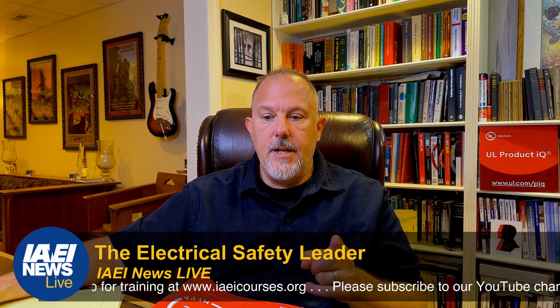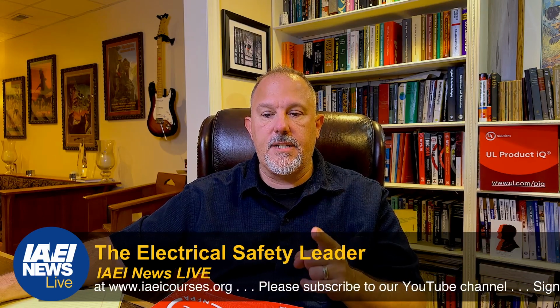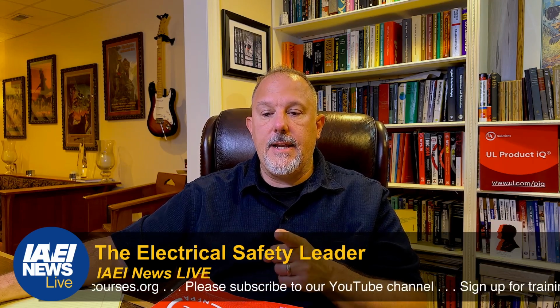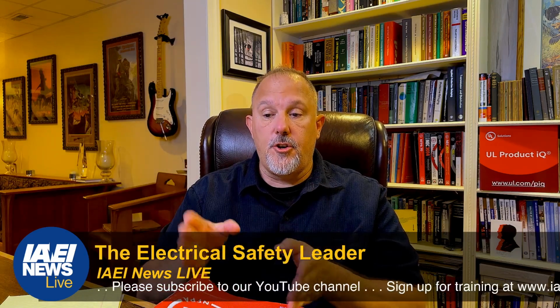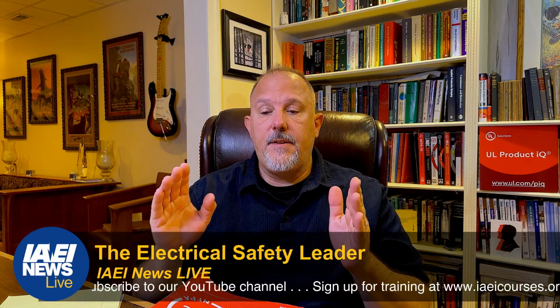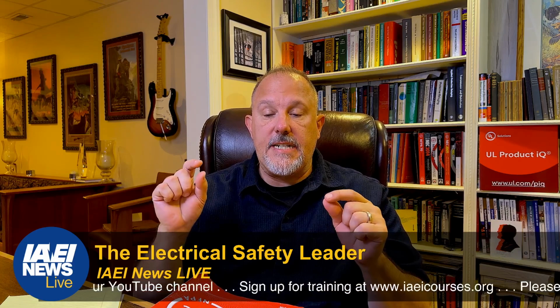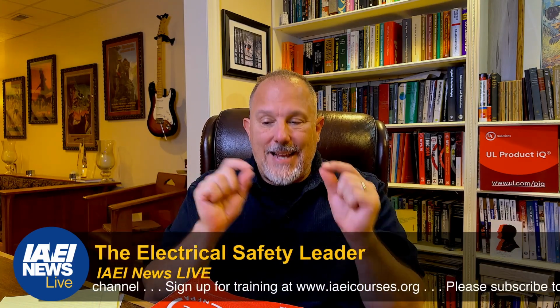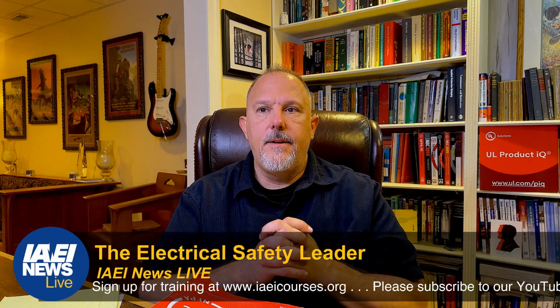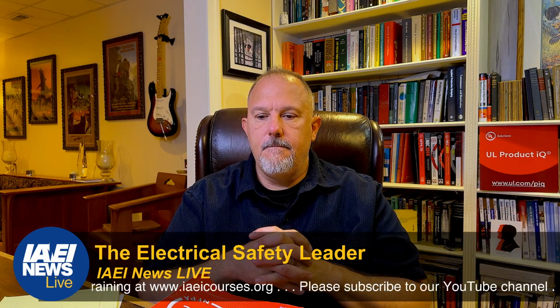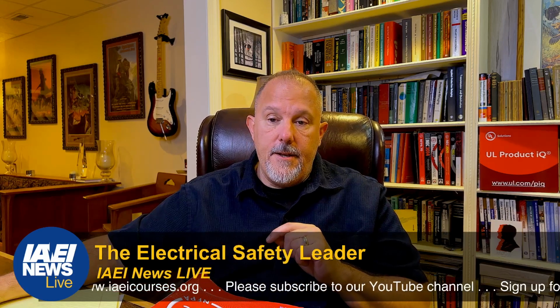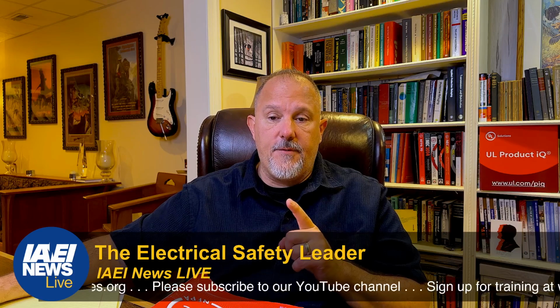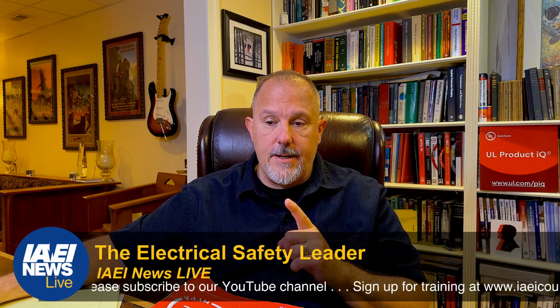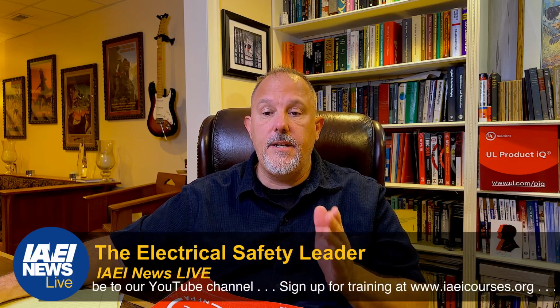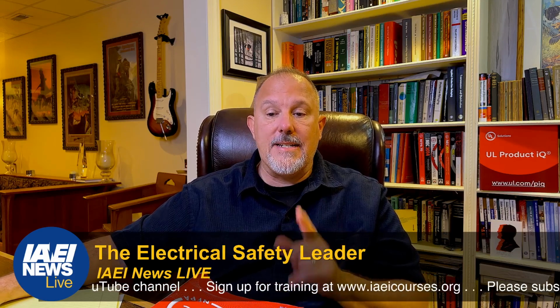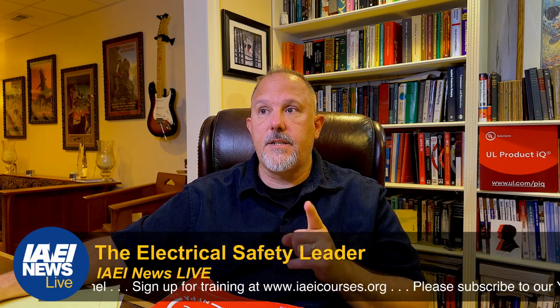related to surge arrestor, and it's found in the definition in section 3.48 of a surge protective device, but it doesn't say surge arrestor, it says secondary surge arrestor. And it says that the SPD basically replaced TVSS, transient voltage surge suppression, and secondary surge arresters. So the word secondary is interesting. But that's the only reference in 1449. And if we look at the scope of 1449, it just says surge protective devices designed for repeated limiting of transient voltage surges as specified to the standard, not exceeding 1,000 volts. Okay, let's go back.